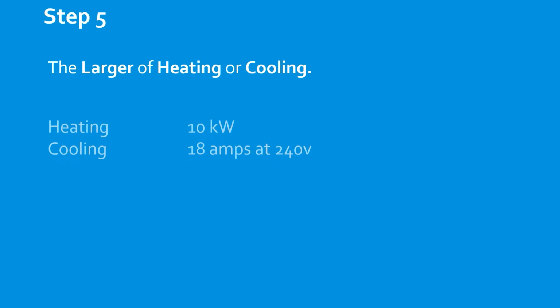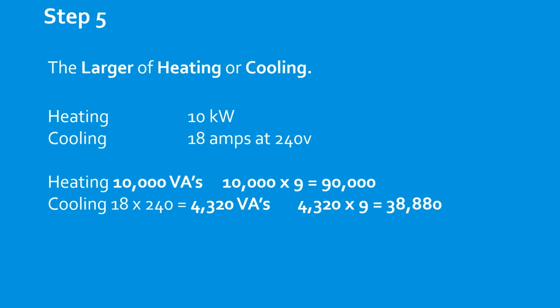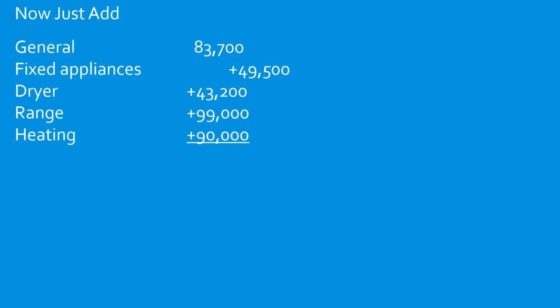Let's do the heating or cooling. Okay, we're going to select the heating. Obviously, you just do simple multiplication. Select the larger. Now we just add them together. Now when doing a multifamily dwelling unit using the optional method, you include the heating or the cooling in the total. So I don't know why they switch back and forth. I guess they assume that once you get over so many units, they're not going to be all coming on at the same time. But in this case, you just group them all together and then apply the demand factor.